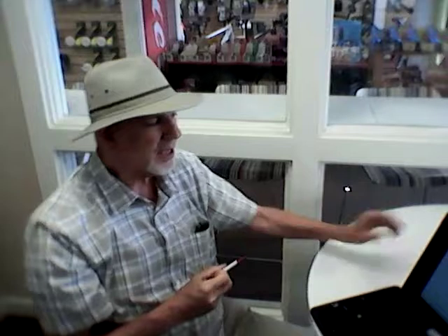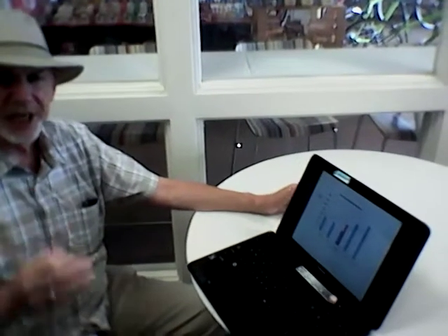Capacity factor figures extremely importantly in wind and solar. Capacity factor is defined as the ratio of the actual amount of energy that would be generated over a period of time, typically a year, divided by the rating in megawatts, which is basically the electrical size of the plant, multiplied times the number of hours in that time period.